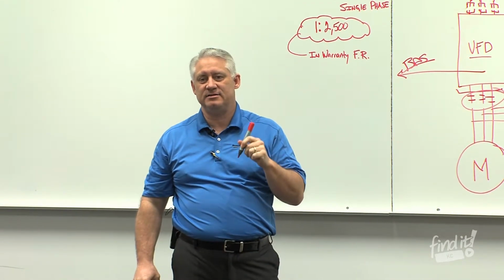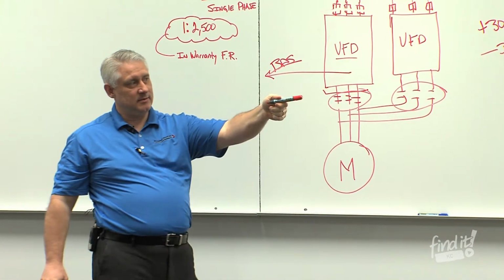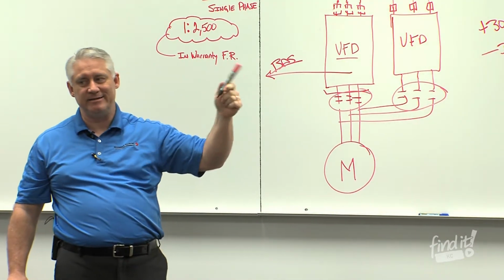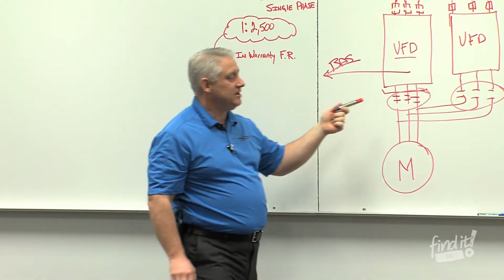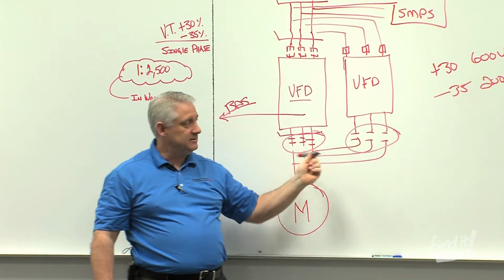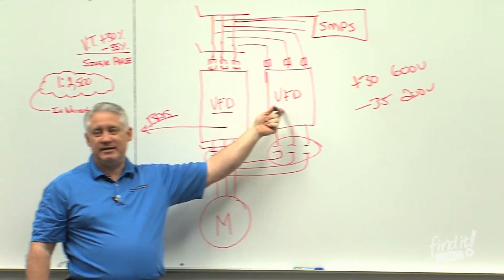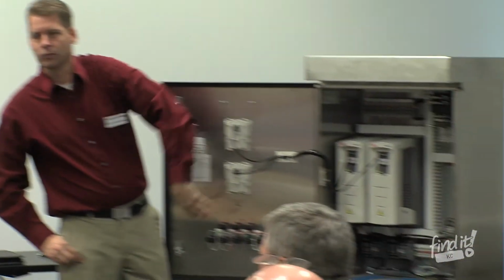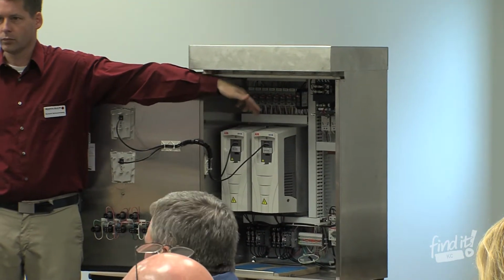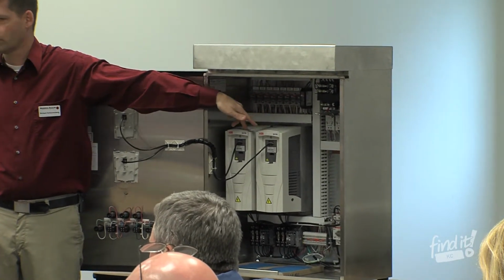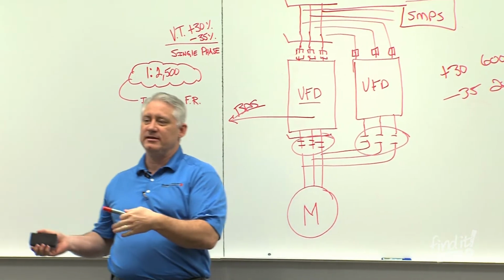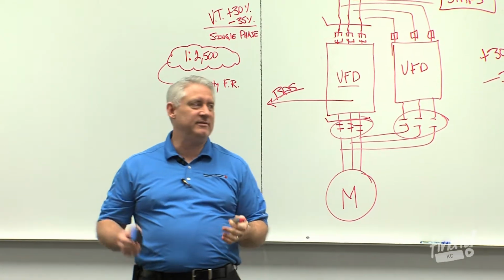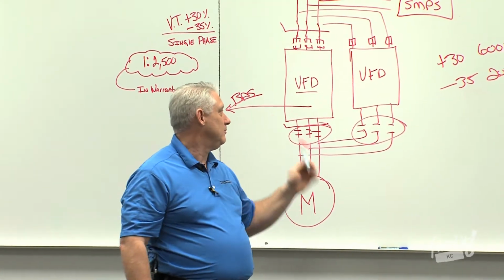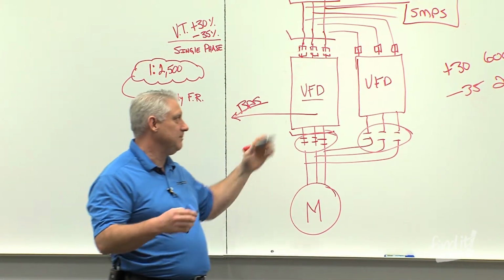The other thing we're seeing a lot more of is customers don't want that constant speed bypass. So that stainless steel NEMA 3R outdoor enclosure there is a redundant drive package. And it's exactly what we've been talking about. It's really everything that a bypass is, except there's a VFD backing up the VFD. So if this drive fails for whatever reason, we auto transfer to the second drive, take care of the problem here, reset it, and it auto transfers back. You can decide which drive is the lead. You can even set that up so one drive is the lead 1 month, another drive is the lead the other month, so we put the common share time on the VFDs for runtime. So that's a redundant drive package, and we're seeing much more of that.